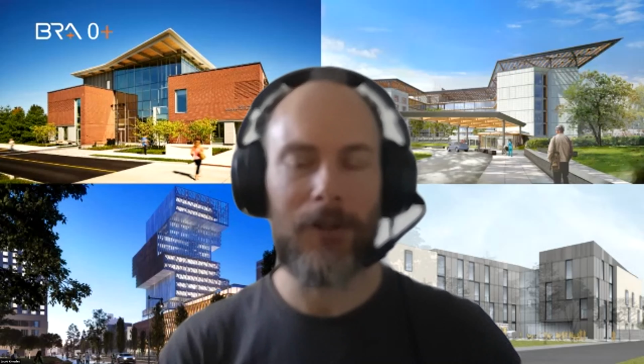You can get a 50,000 square foot office building down to the point where it probably makes sense just to do air source, or the bore field would be maybe 10 boreholes at 500 feet each. So it really depends on how low you can drive those loads, the program of the building, and your interest in whether you want the extreme long-life system of the geothermal system.